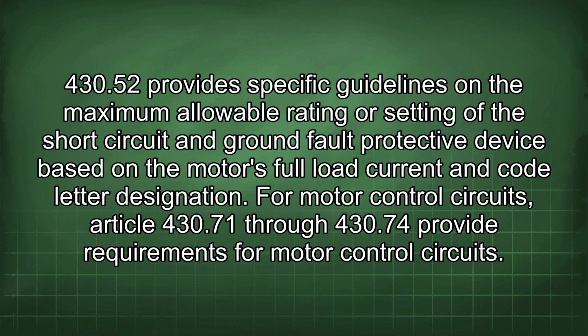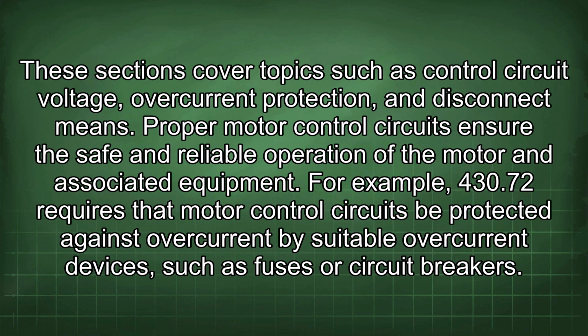430.52 provides specific guidelines on the maximum allowable rating or setting of the short circuit and ground fault protective device based on the motor's full load current and code letter designation. For motor control circuits, Article 430.71 through 430.74 provide requirements for motor control circuits. These sections cover topics such as control circuit voltage, overcurrent protection, and disconnect means. Proper motor control circuits ensure the safe and reliable operation of the motor and associated equipment.